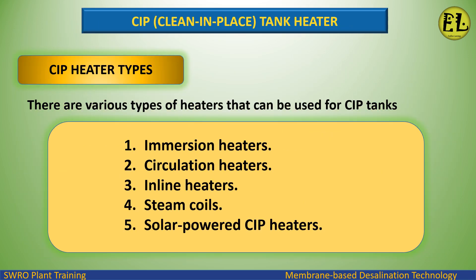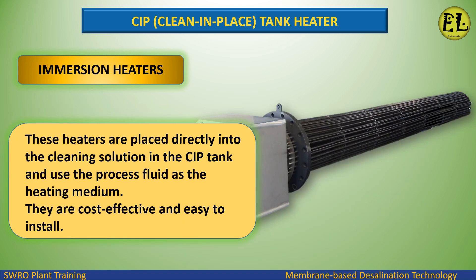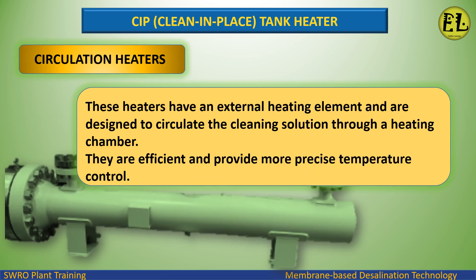There are various types of heaters that can be used for CIP tanks: immersion heaters, circulation heaters, inline heaters, steam coils, and solar-powered CIP heaters. Immersion heaters are placed directly into the cleaning solution in the CIP tank and use the process fluid as the heating medium — they are cost-effective and easy to install. Circulation heaters have an external heating element designed to circulate the cleaning solution through a heating chamber, providing more precise temperature control.